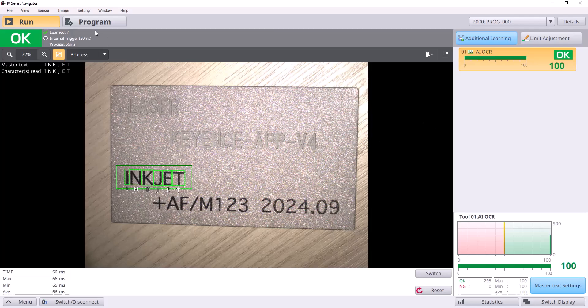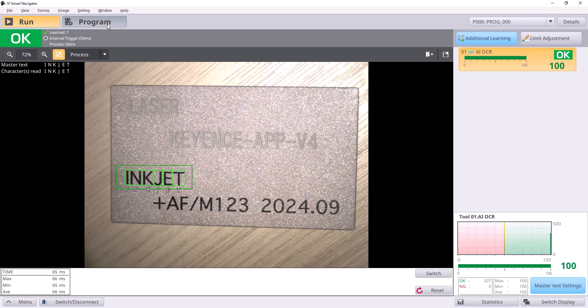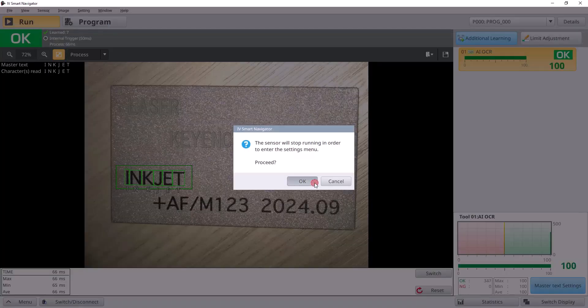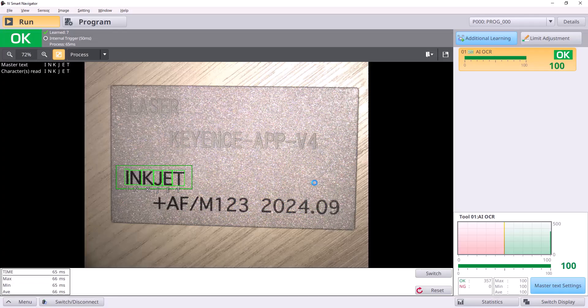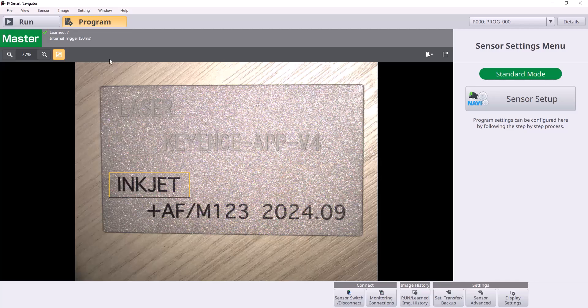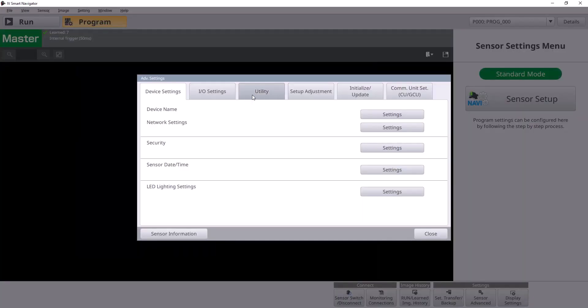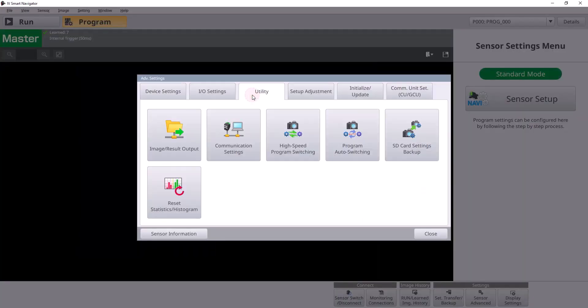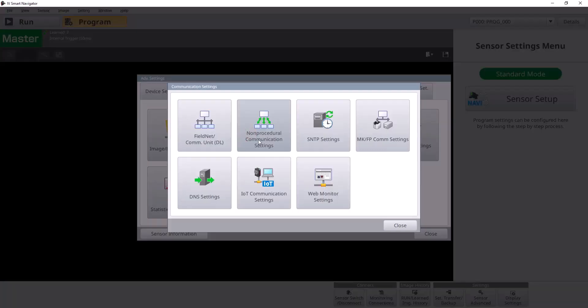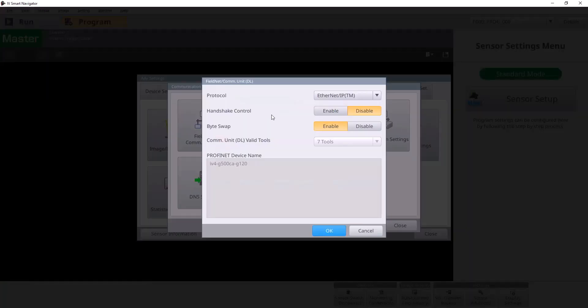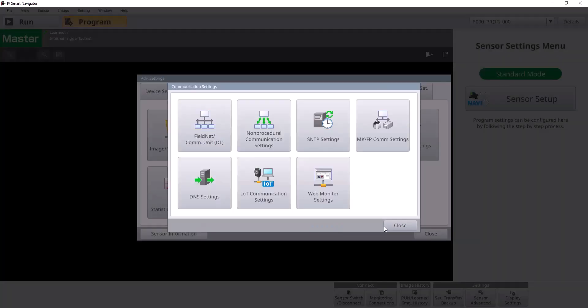Before we jump into the PLC side of things, there's one setting you'll want to make sure you have turned on that'll make this process a lot easier for everyone. You can put it in program mode and go to sensor advanced and then in utility under communication settings and the field net comm unit settings, you'll want to make sure you have byte swap enabled.